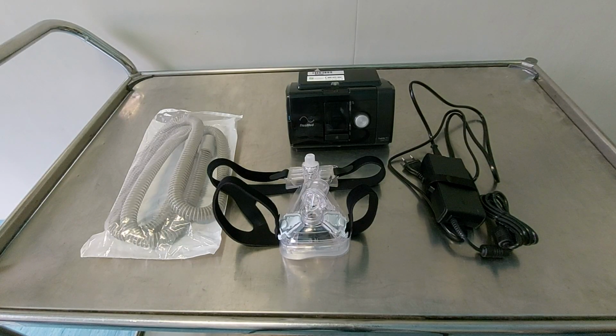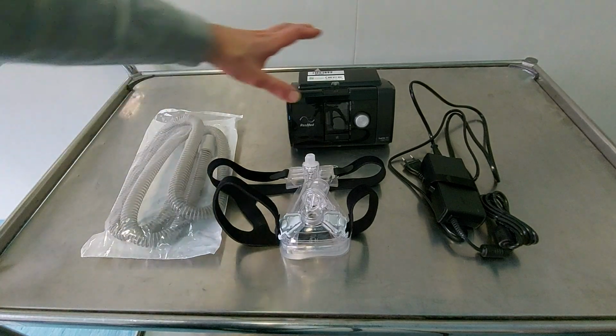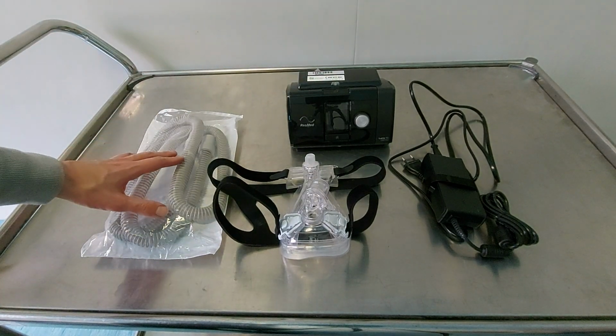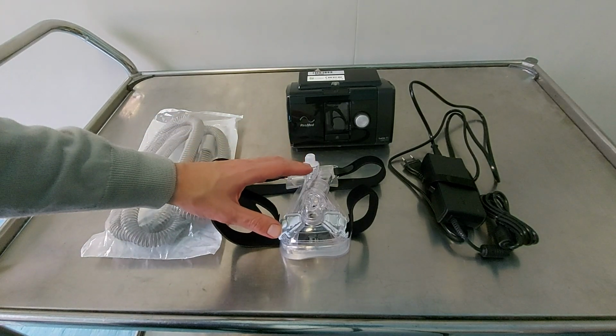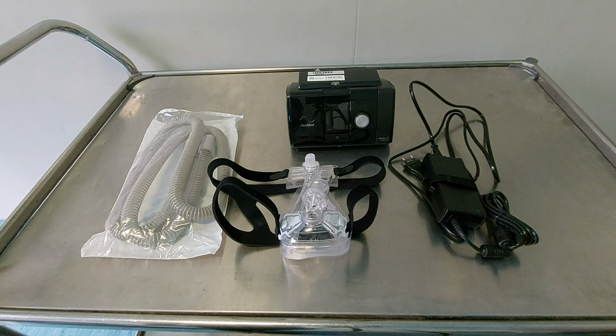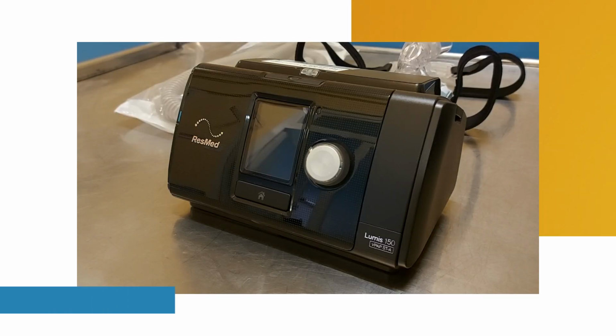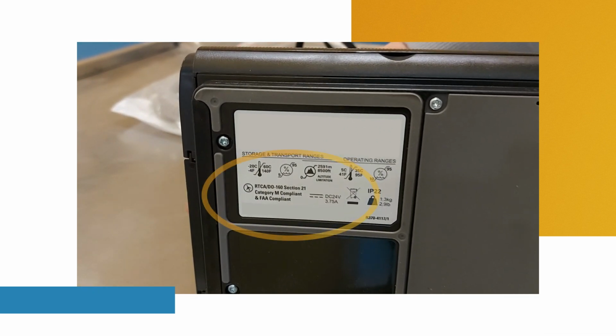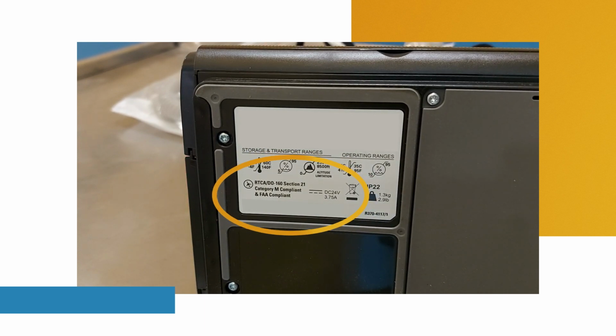These are the essential parts of the CPAP and BiPAP therapy: the machine itself, tubing that connects the machine to the face mask, and the face mask that the patient will wear, which is attached to headgear. Check the voltage, current, and frequency requirements for the device. This is typically found on the metal faceplate on the back of the device or in the manual. Ensure that the electrical power is at the same voltage and frequency and the device's current requirements are met by the electrical distribution system. Also, verify the CPAP or BiPAP's electrical power cord plug is compatible with your electrical outlets.